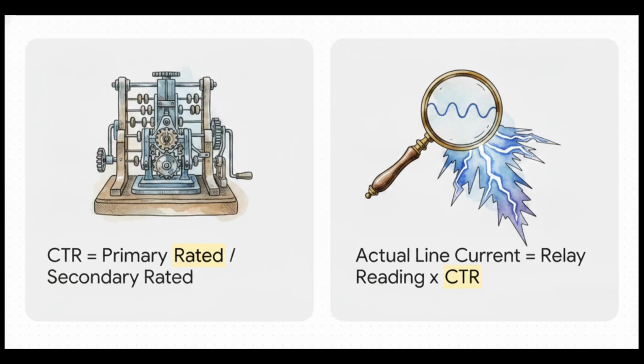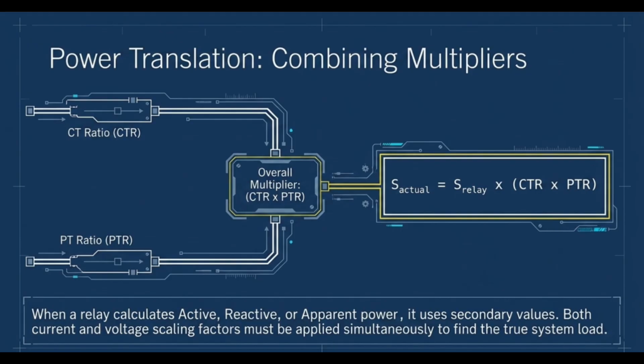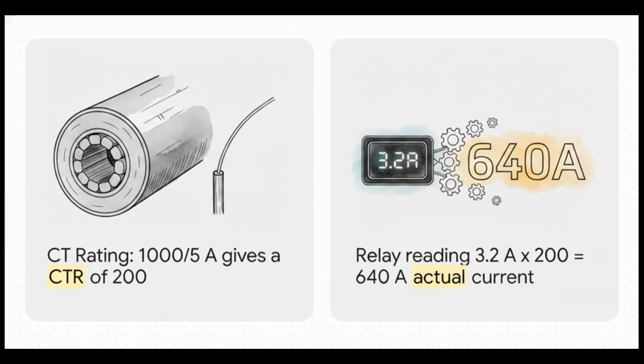Now, to figure out what's actually happening out on the live wire, the relay relies on the CT ratio, or CTR. The formula is beautifully straightforward. The CTR is just the rated primary current divided by the rated secondary current. To calculate the actual, real-world danger out on the line, you just take the relay's safe reading and multiply it by that CT ratio. Let's put this into practice.